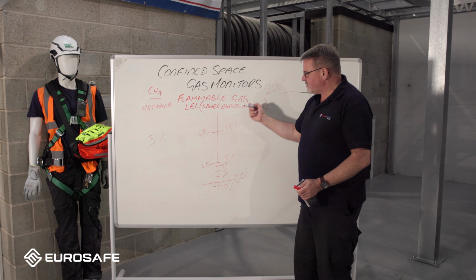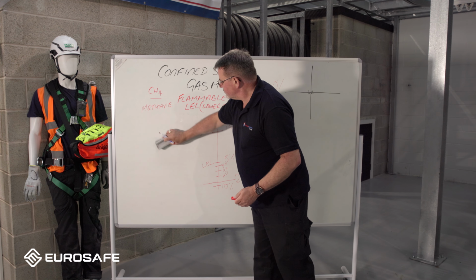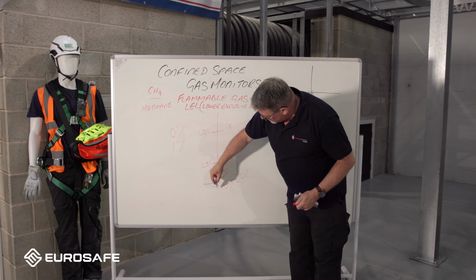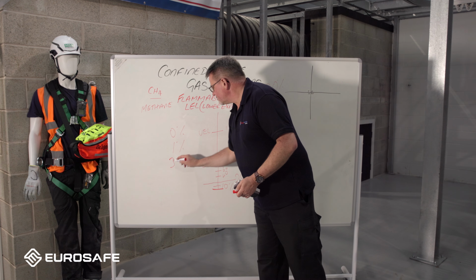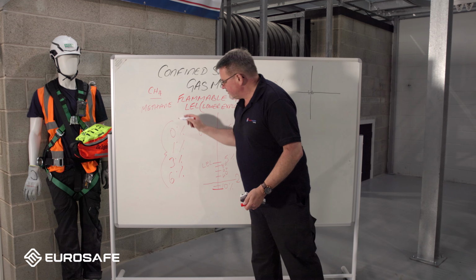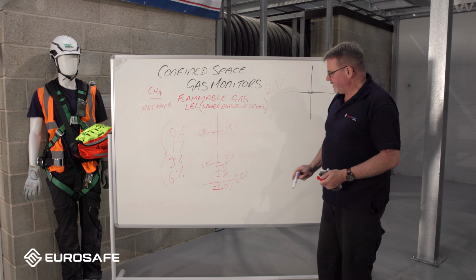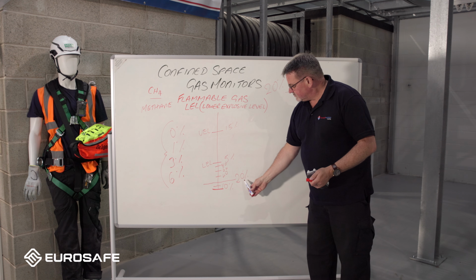So in the grand scheme of things, when you have me in the hole, you're now my entry controller at the top, and I'm giving you a reading. What's your LEL reading? 0. It's good. 5 minutes later, 1. Look at the grand scheme of things, it's right down there. That's your reading. 5 minutes later, 3%. 5 more minutes, say 6%. But we still use the same concept. If conditions change, we need to get out and reassess. So again, we're reading your flammable gas. Methane is what we look for, and that's your concept and how we are in the actual confined space. That's when the alarm goes off, down here.